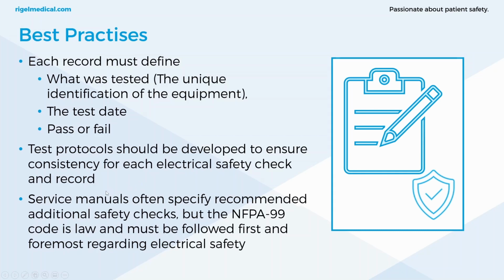So the aim of electrical safety in NFPA 99, and that of all electrical safety standards, we know that it's to limit leakage currents that can cause injury to a patient or user. So it's always best practice to keep that risk of electrocution to a minimum, regardless of what the minimum requirements are in the standard or code.